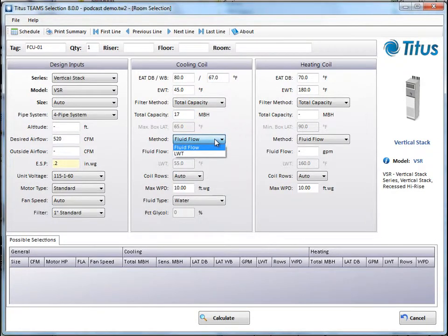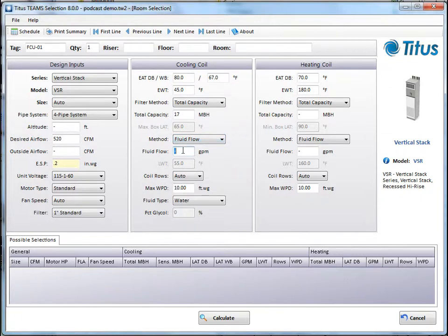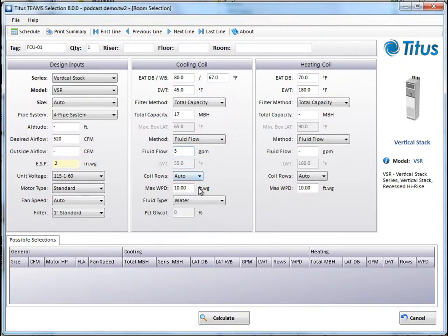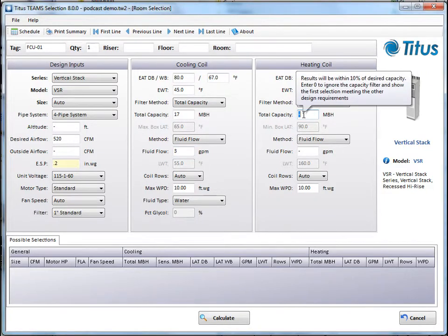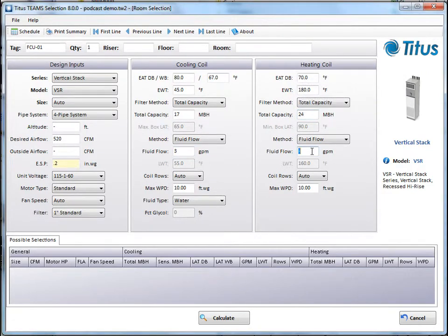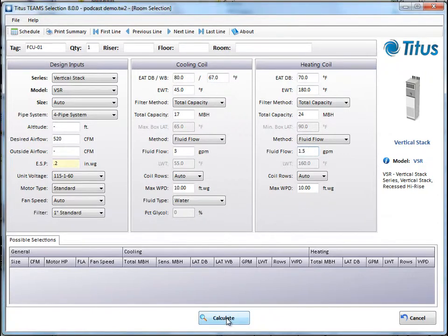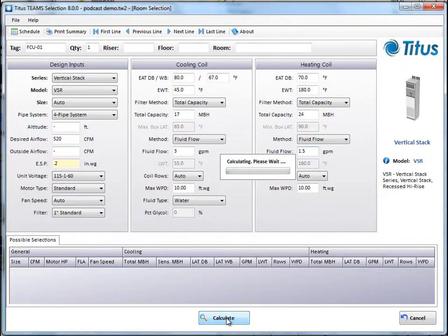So back to our selection. Next you need to tell it the fluid flow or the leaving water temperature. We'll put in 3 GPM. We'll leave the rest as it is. We'll let it select the number of rows for us, and we've told it that there's a max water pressure drop of 10 feet, and where fluid type is water. Now let's go over to heating. We'll do the same thing. Let's put in a capacity of 24 MBH, and we'll say 1.5 GPM. Once you put in your inputs, you just click calculate.